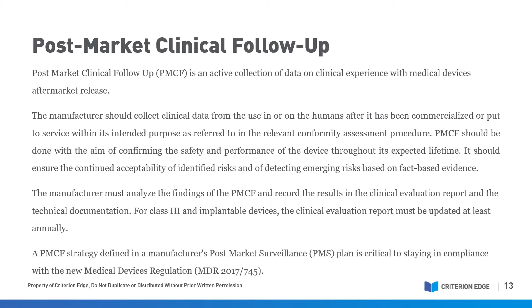And again, referring back to the IVDR requirements, according to Annex 13 in the IVDR regulations, the PMPF is going to be that continuous process, just as we saw with MDR. When conducting your PMPF, you are aiming to proactively collect and evaluate performance data, but also any relevant scientific data from the use of your device when it's used within its intended purpose or purposes, and as it's referred to in your conformity assessment procedure. So ultimately, your goal is to confirm the safety, performance, and scientific validity throughout the expected lifetime of the device, and to ensure that you continue to be acceptable in terms of your benefit-risk ratio. And your goal really is to detect emerging risks on the basis of factual evidence.